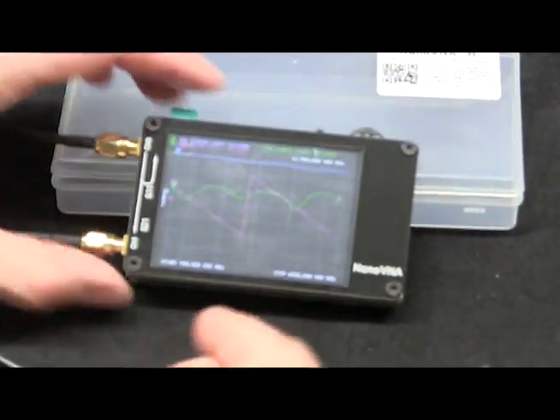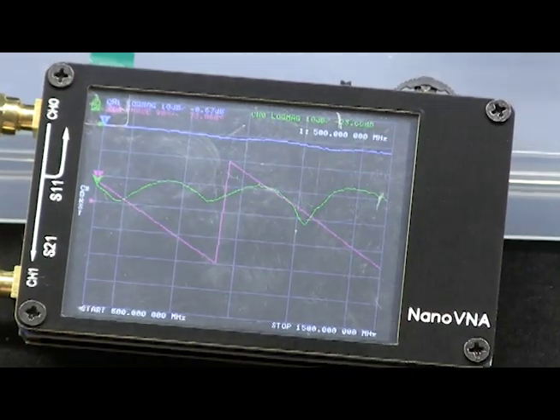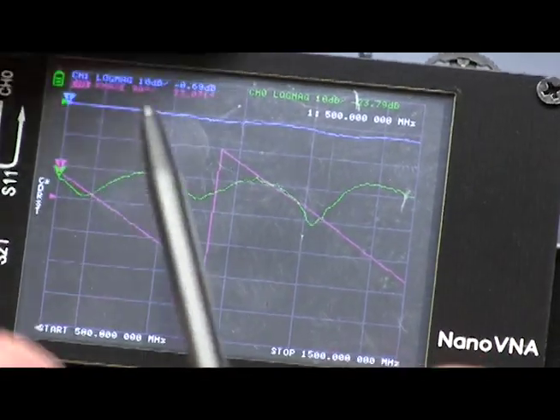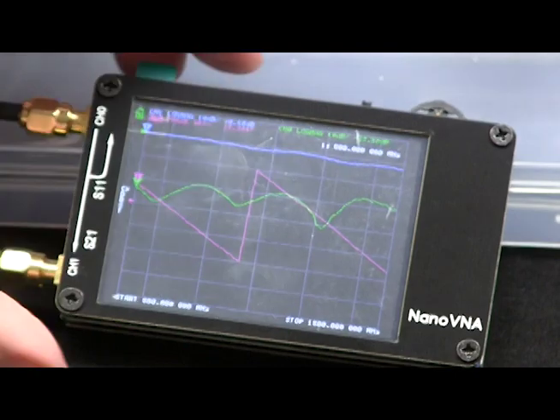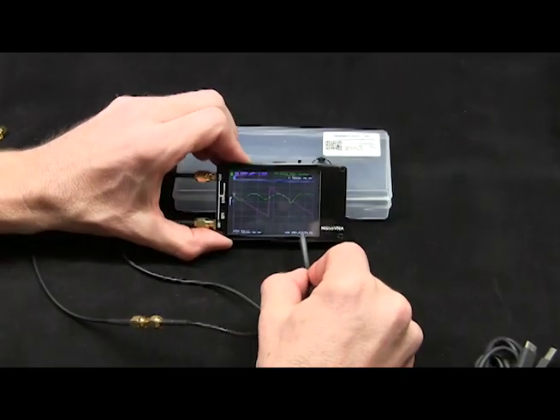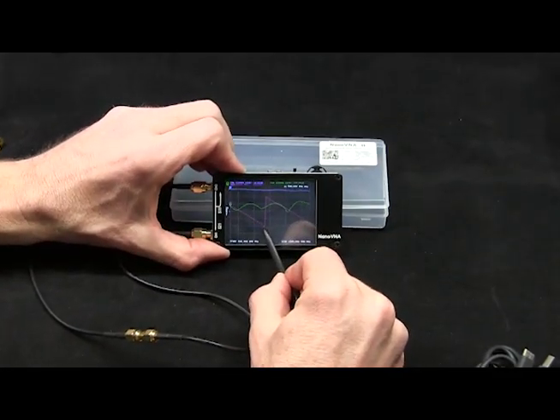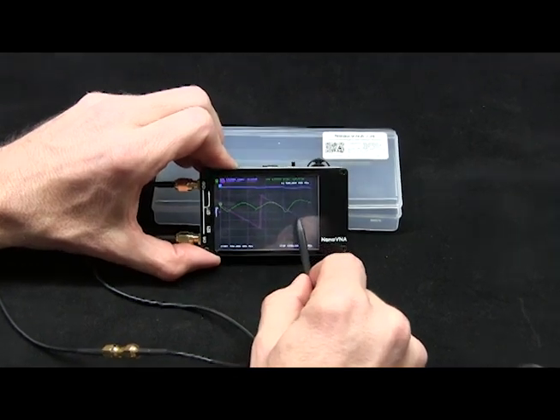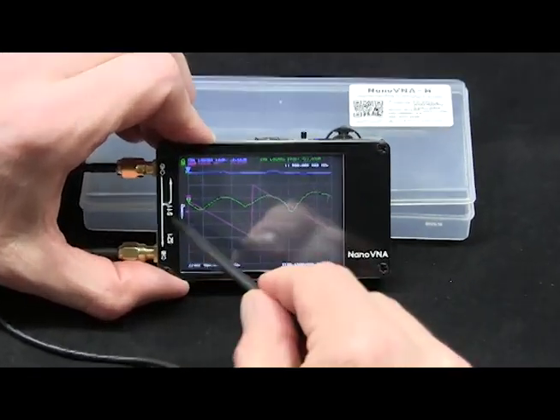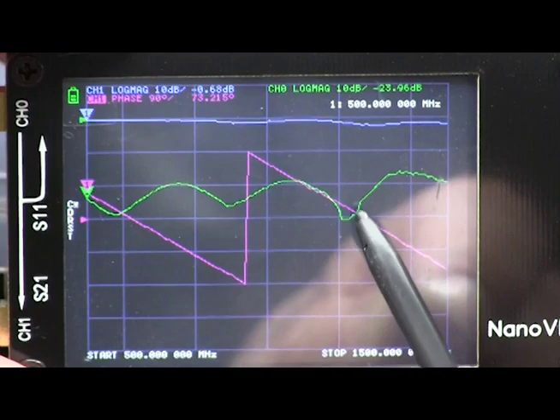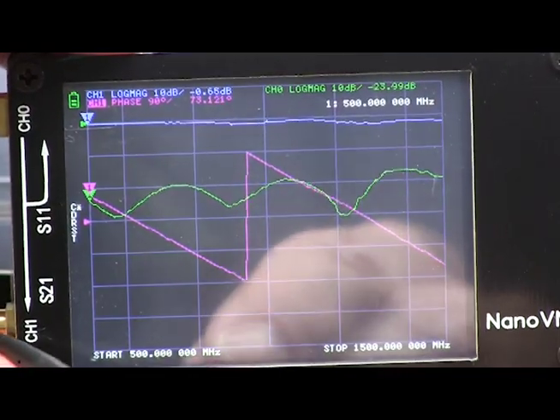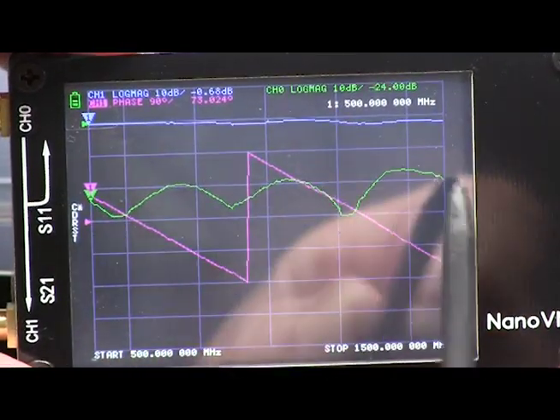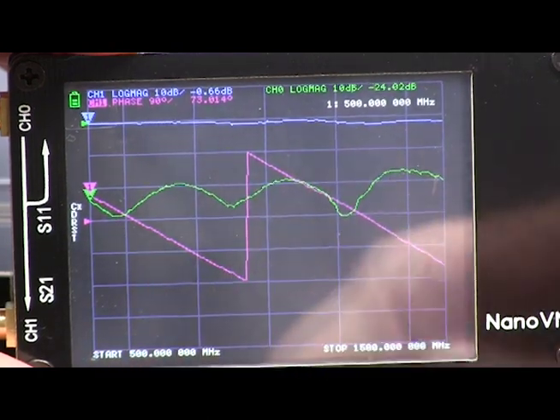So now we've connected up, and what we can see is we're measuring the phase shift between the end of our first cable through this second cable. The phase shift through here is fixed in time, but since we're sweeping in frequency, you can see that our phase changes relative to the frequency. You can also see that our S11 has these peaks. These are the times we go from an open to a short, an open to a short. Now this is 50 ohms, so S11 is pretty low, but we can see a little bit of the artifacts.